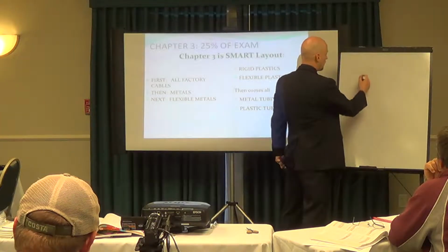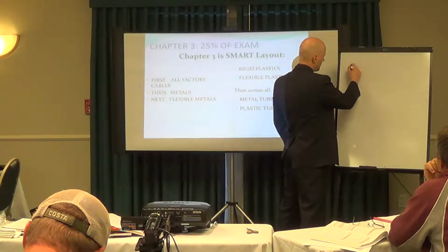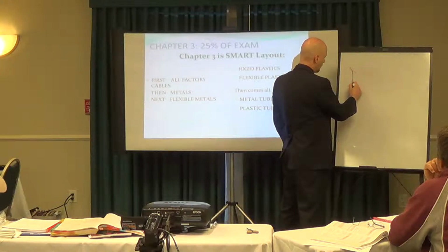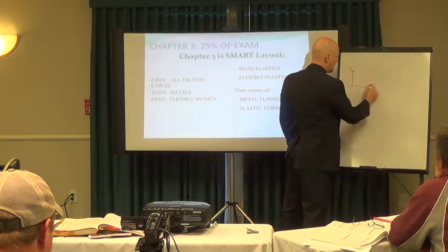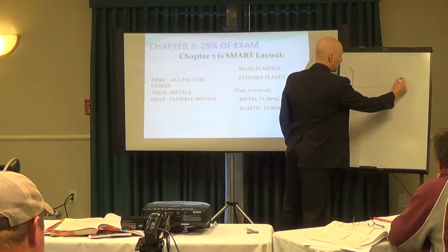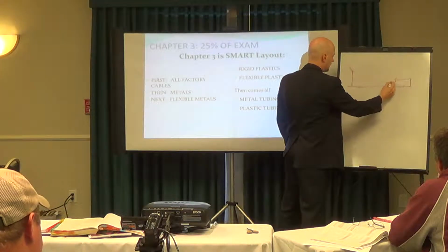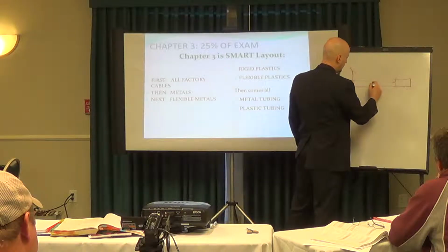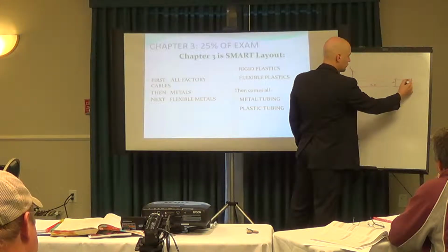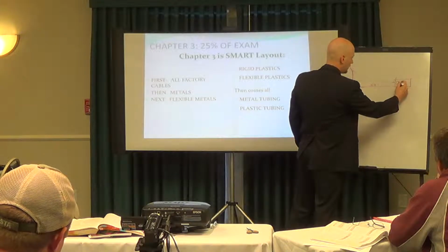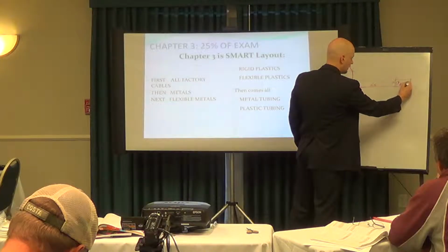It has to do with a generator, and they're giving you a building, and they're asking you right here where those conductors come underneath the building, and these conductors are fed from a generator on the back out here. And they tell you that this is within sight of the building, so you can see from here to here, and it's 55 feet. This generator's got a disconnecting means mounted where it's accessible, readily accessible, and it's integral to the ATS. So you got an ATS and a disconnect right here.